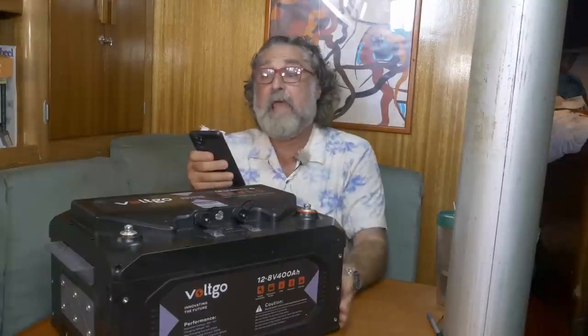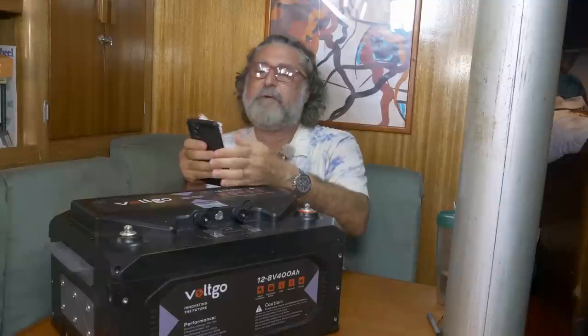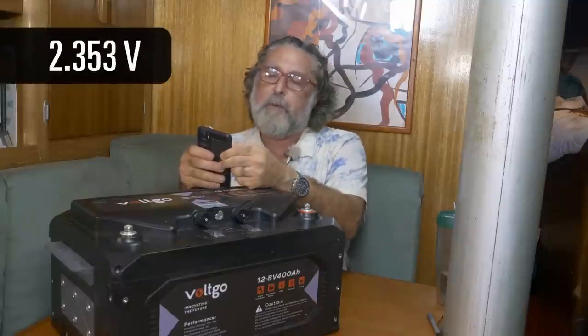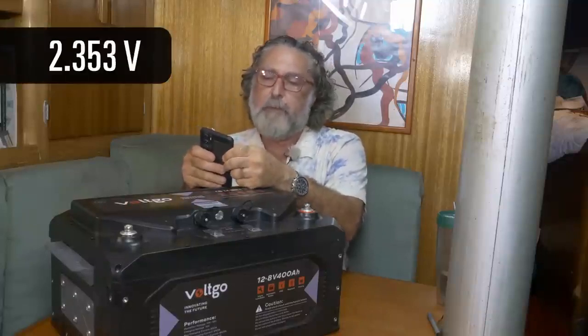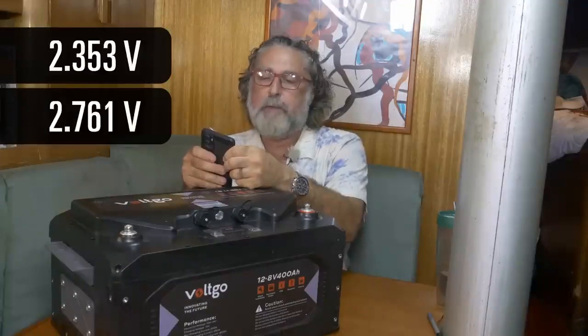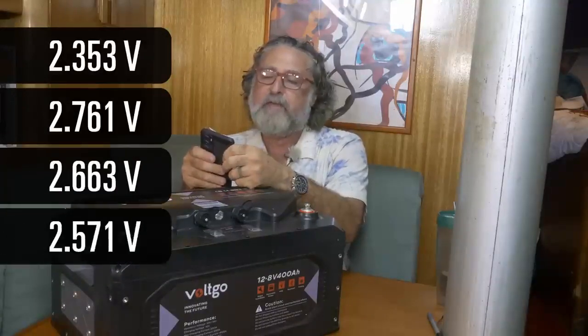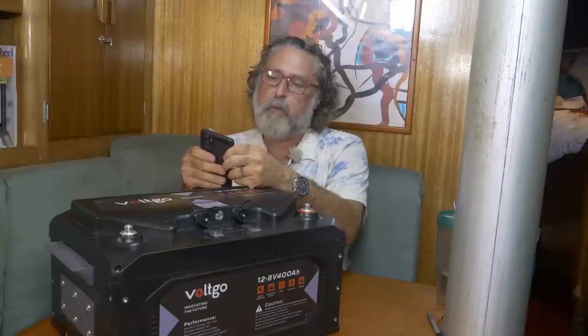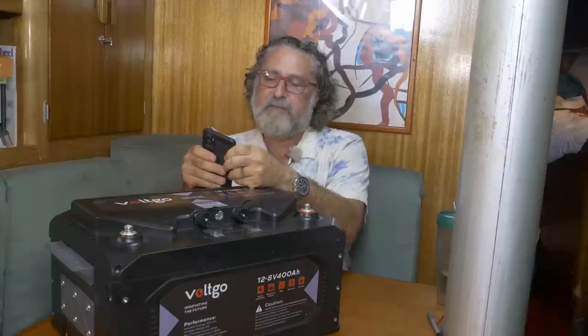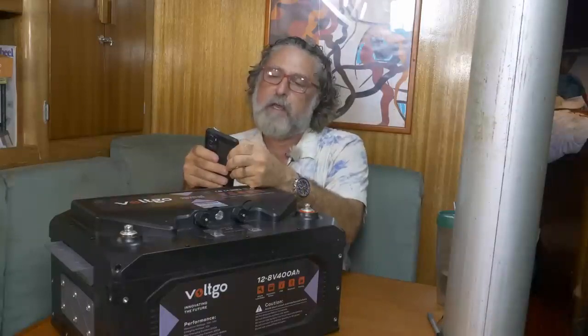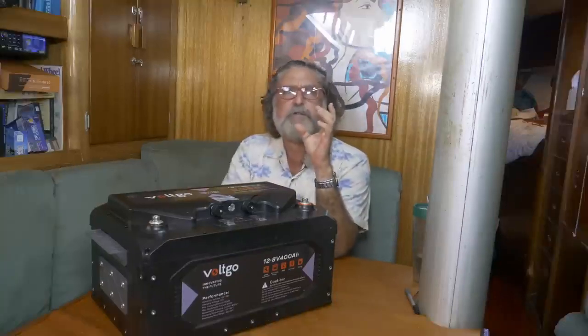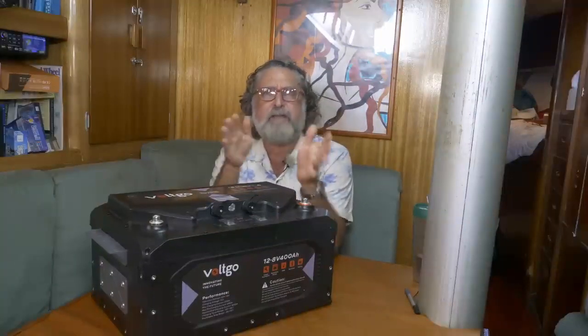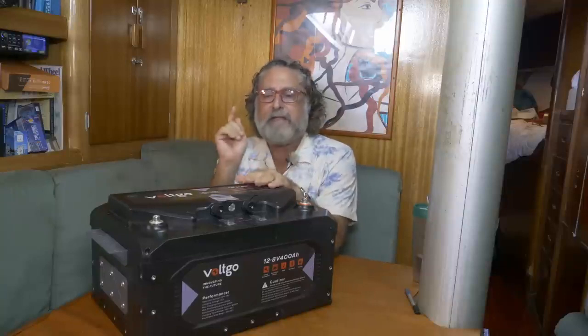Well, at the end, the battery cell voltages were 2.353, 2.761, 2.663, and 2.571. What does that give us? The highest was 2.761 and the lowest was 2.353, giving us a larger differential in cell voltages than we got at the high end. That's telling, and it's good.